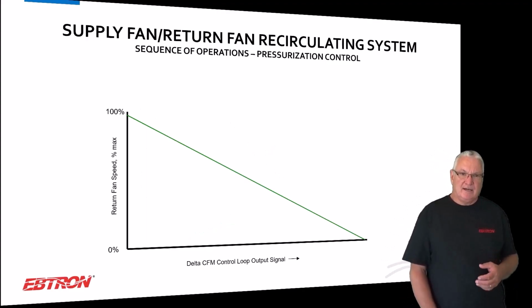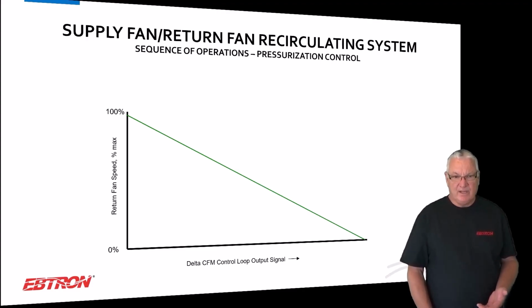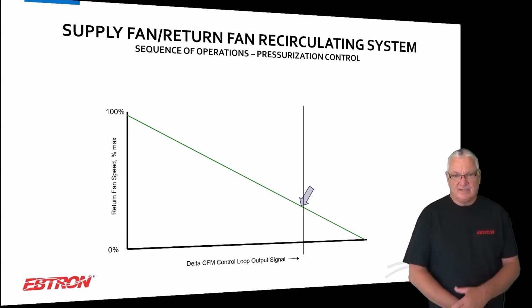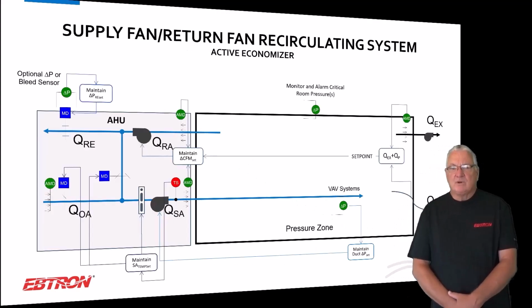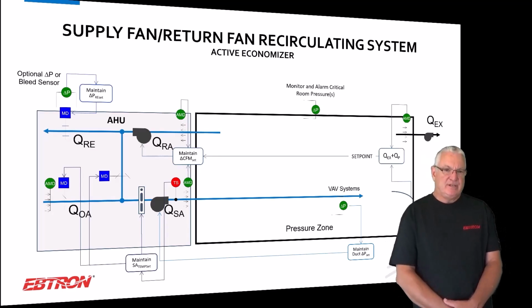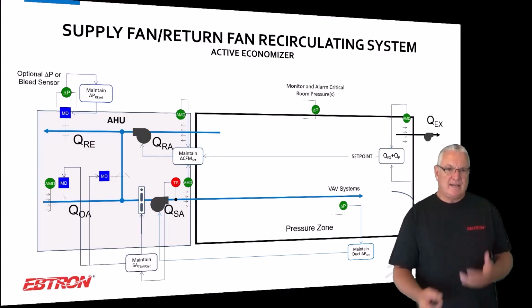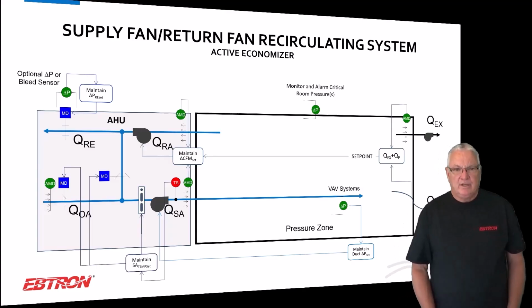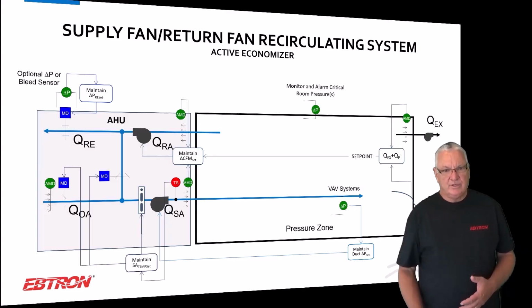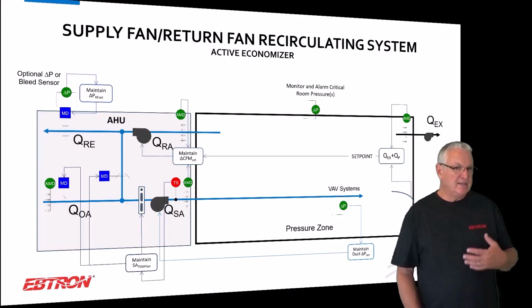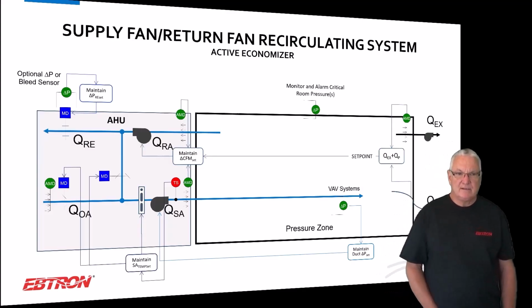How the return fans actually work is pretty straightforward. In this case, if we need to increase the differential, we decrease the return fan speed, okay? When we're economizing, it's not that much different, except that instead of the outside air being controlled to the outside air set point for dilution, you're basically controlling to your supply air temperature, and then you're really using the outside airflow station as a low limit device to switch you back out of economizer mode into minimum outside air mode.